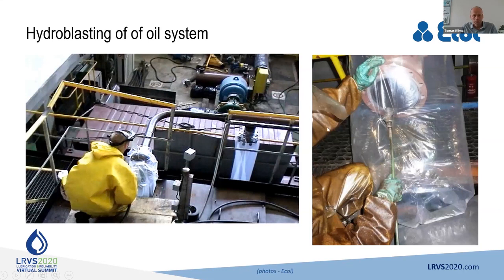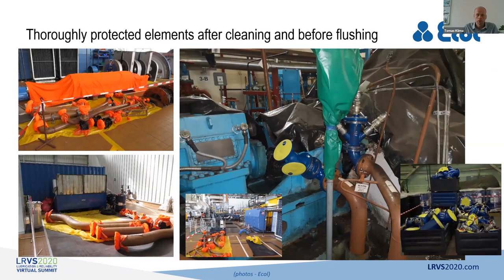Hydroblasting looks almost the same on every one of my pictures. However, it is visible that we take care of the waste, and it needs some knowledge how to clean the pipe, where to start, where to finish, and how to do that. A small insight into the work culture of our employees, where the openings need to be secured, because if you clean it, you want to keep it clean during all your other works. Also, before the flushing, where the pipes are prepared for flushing, for installing the jumpers and bypasses, you need to take care to protect it, because this is ongoing with other works and other companies.